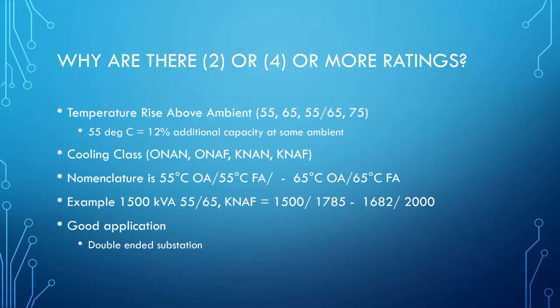The ANSI standard is 40 degrees C continuous over a 24-hour period and a 50 degrees C maximum. If you are in the desert or somewhere where that ambient temperature is higher, say it's continuously 50 degrees C or with a maximum of 60 degrees C, you would want to specify a 55 degrees C transformer. The other rating is the fan rating.